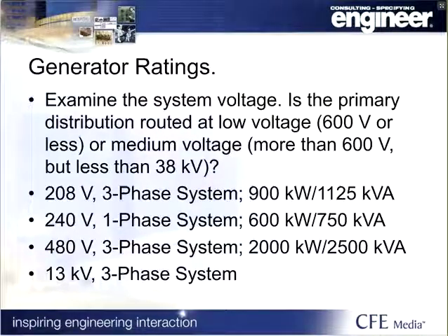The generator ratings should be coordinated with the primary distribution voltage for the property. Below I've listed some common distribution voltages, and the maximum generator rating I would typically recommend based on not exceeding a 4,000 amp distribution bus. If the required capacity is any larger, I'd recommend either breaking up the EPS into multiple systems or stepping up the EPSS distribution voltage to reduce costs. Medium voltage distribution may be considered for generator systems intended to support a campus or large hospitality resort, and step down to utilization voltage where appropriate.